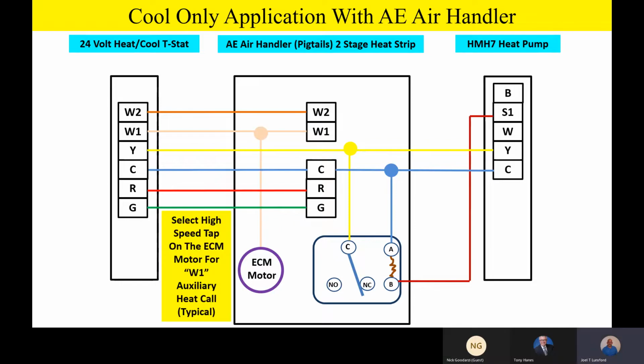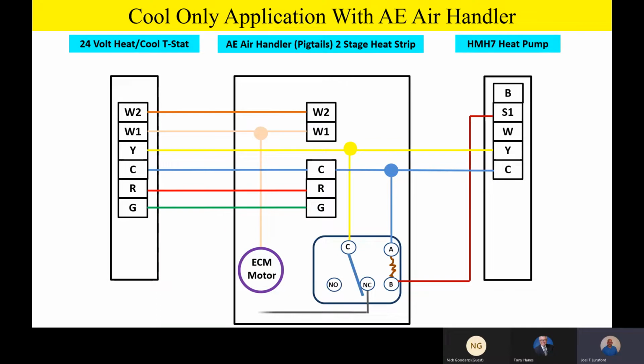And then again, because we want to make sure and drive that indoor fan to high speed anytime we have a heating call. So if the thermostat calls for heat, maybe it's a mild day, maybe we heat in the morning and we cool in the afternoon. That can happen sometimes in certain parts of the country. So it's cool in the morning, we have heat on, then the thermostat calls for cooling operation. But anytime we call for heating, we're going to drive that indoor motor to high speed. Then on the normally closed contact, just like we had before, we're going to select 100% airflow on the ECM motor. And then on the normally open contact, we're going to select 60 to 65% cooling airflow.